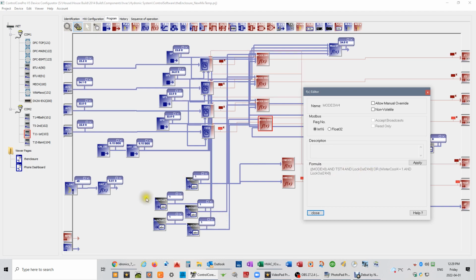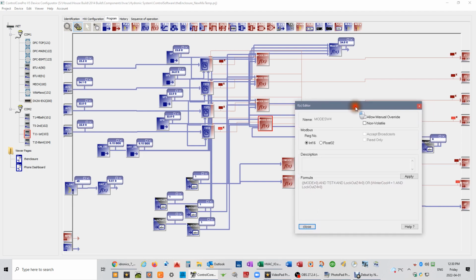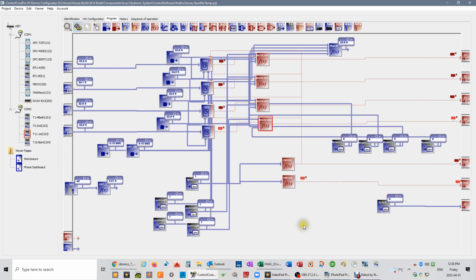I'll explain that in a second here. Or are we in winter cool mode and lockout is greater than 0? So this is just a further gate to determine, do we really want to turn the heat on, or more specifically, do we want to turn the actuator on? Because there's going to be times where we're turning the actuator on to actually extract heat from the room, even though we're above that set point.